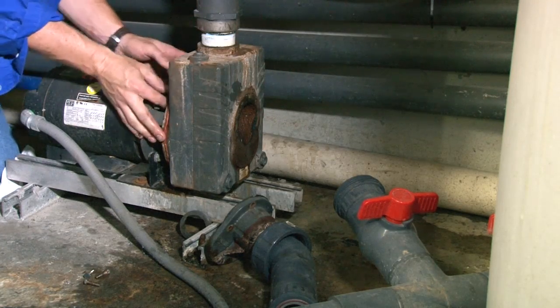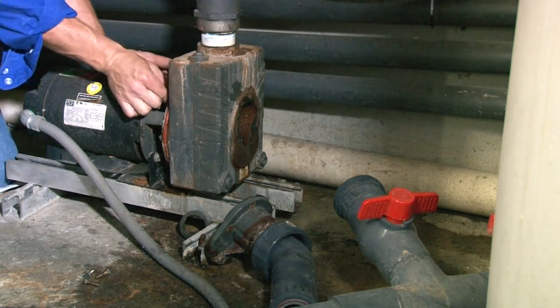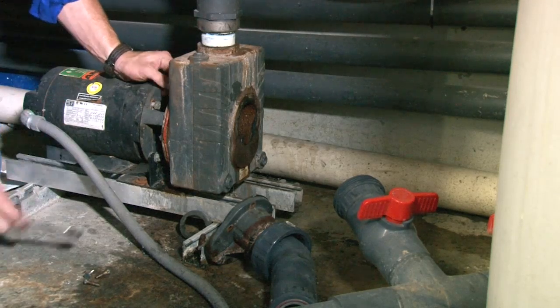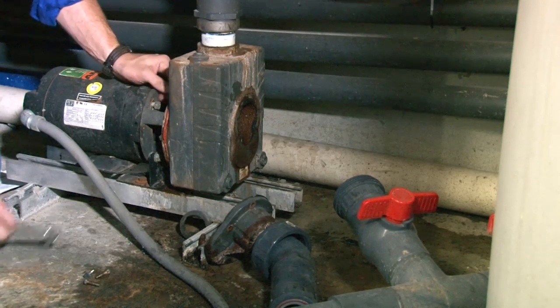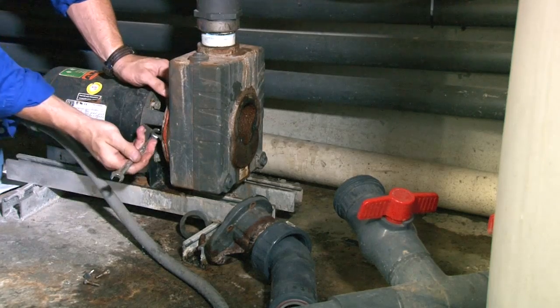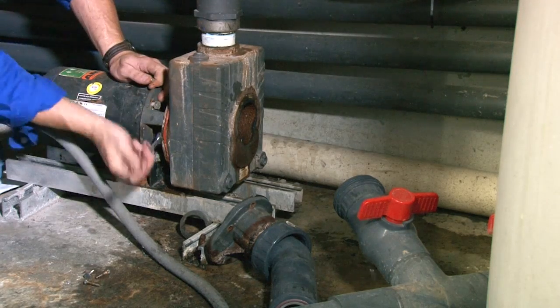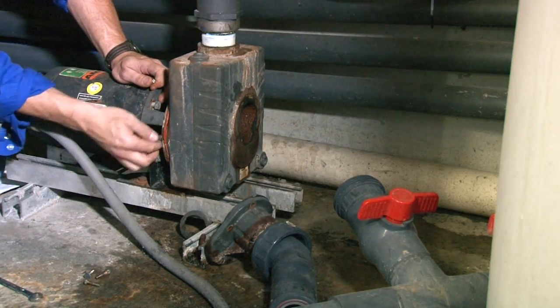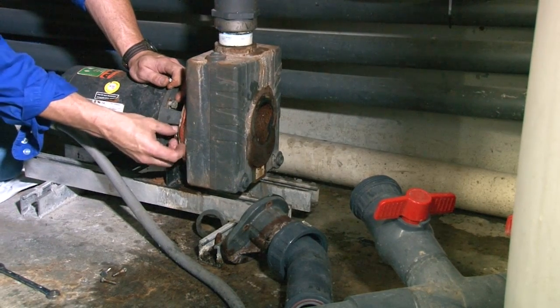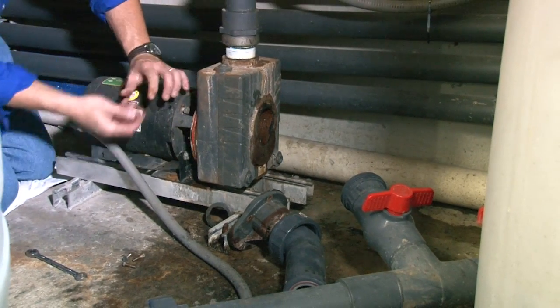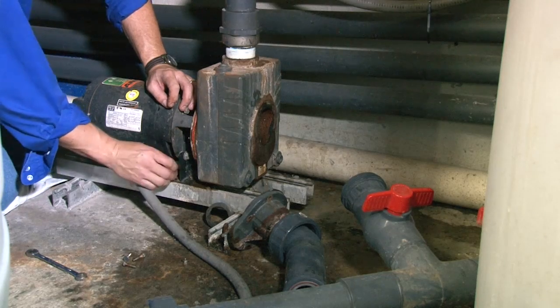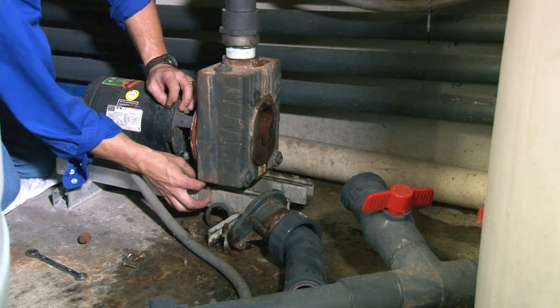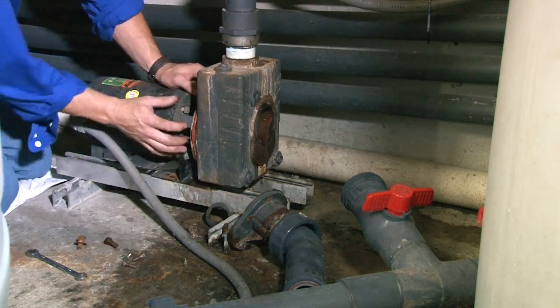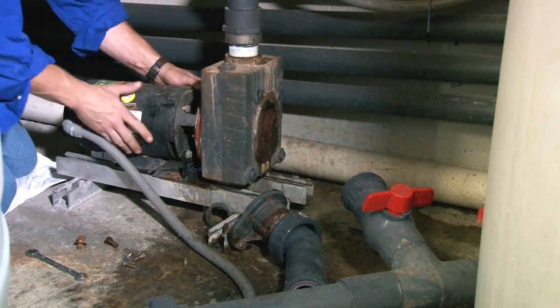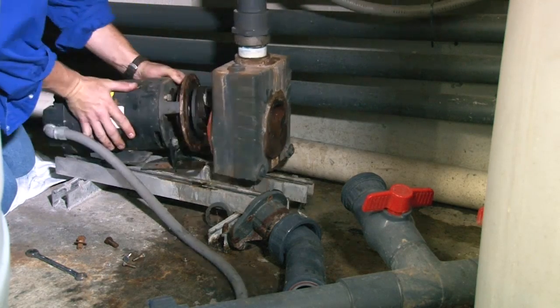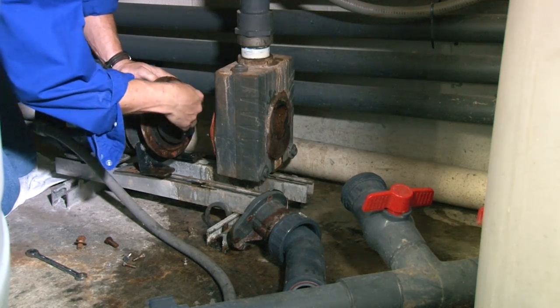And now I've got to pull the pump motor out of the head. So there's another 7/16 nuts on the back. So I'll take those off. And I've already got most of them off already for the video. But I've got to take off the 4 bolts that hold the motor to the motor frame. And then my motor will back out from the head. And there I found my clog.